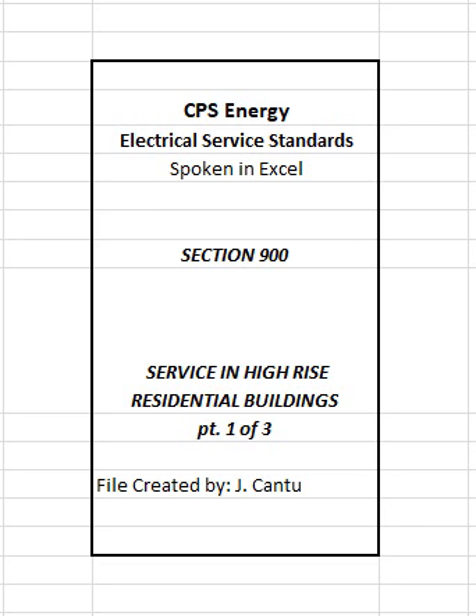903 Primary Voltage Distribution System. Refer to Figure 902. Where customer determines that it is not feasible to have a secondary voltage distribution system and still meet CPS Energy's voltage drop requirements in a high-rise residential building, then customer may request a primary voltage distribution system. This type of installation typically involves a primary 3-phase pad mount switchgear and 3-phase pad mount transformer installed by CPS Energy at ground level outside of building.